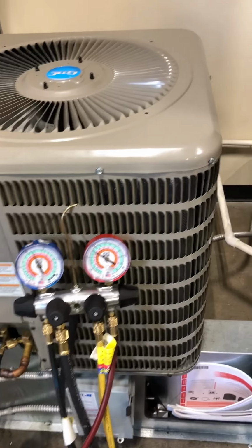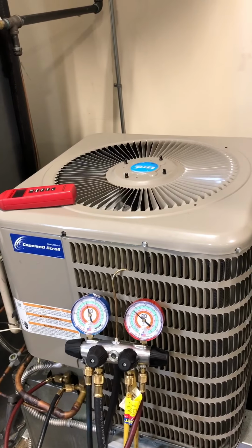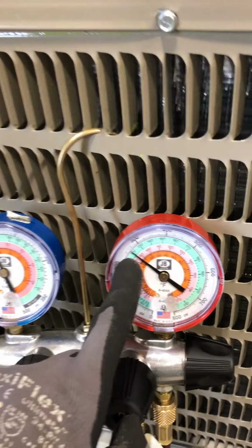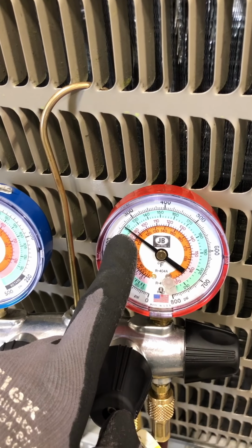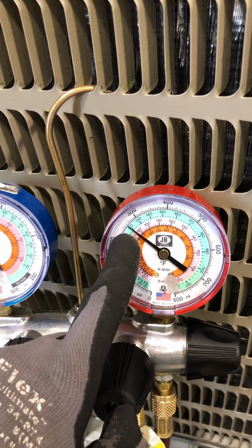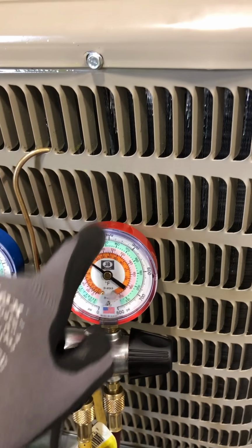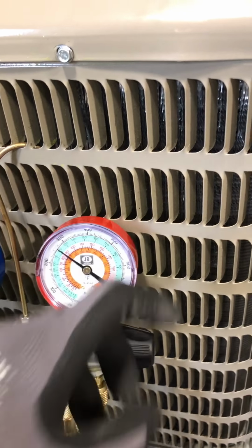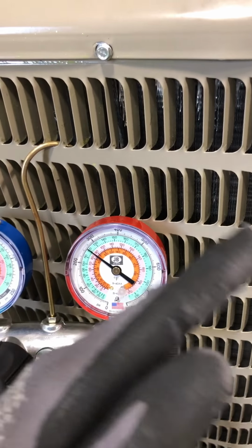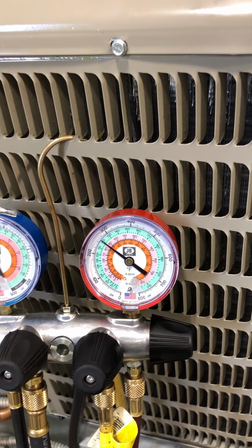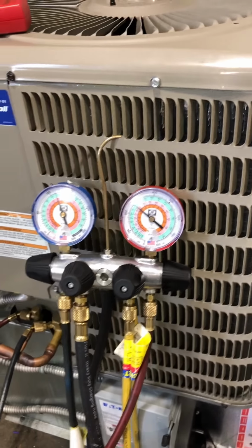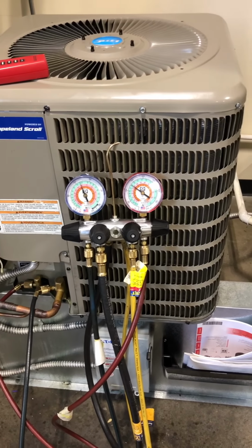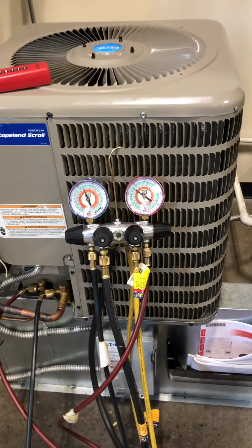And our condensing split: the ambient temperature, the air that the condenser is using, and my condensing temperature. The difference between the two is our condensing split. The higher that condensing split is, the less heat we're removing from this refrigerant in the condenser. The more heat it's retaining, the higher that pressure is going to go. We have to check all of those things, guys, before we can make a determination that, yeah, it's low on charge, or it's overcharged, or there's an airflow problem. We have to check all those things.